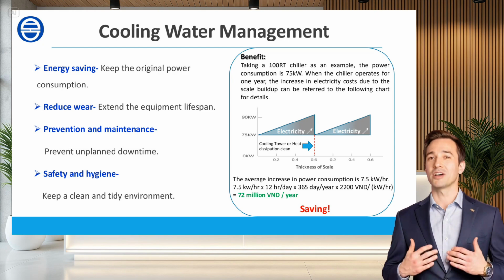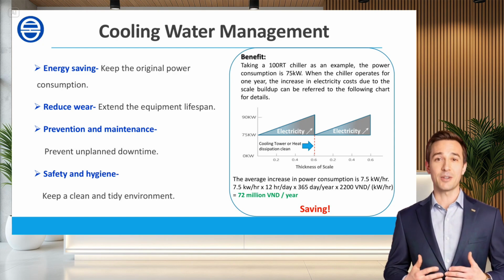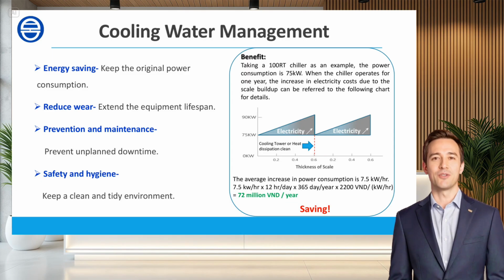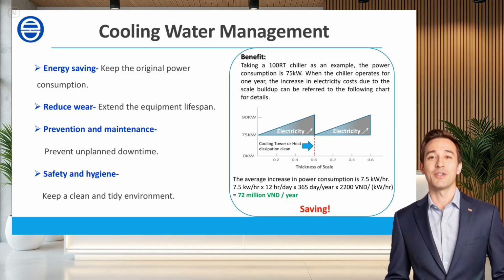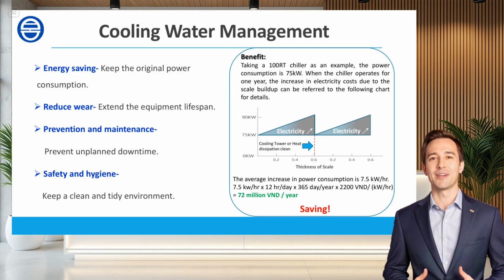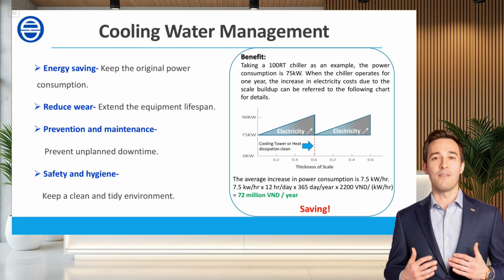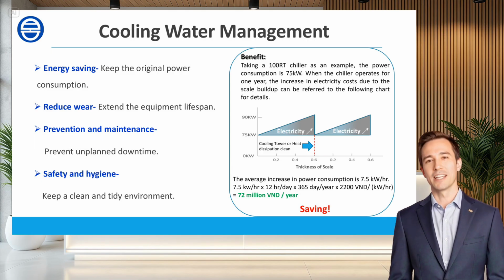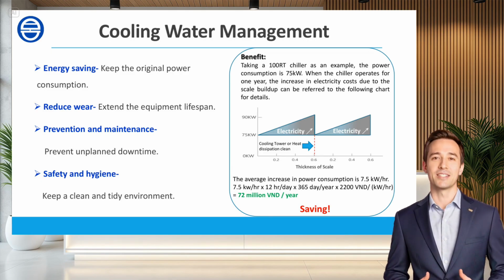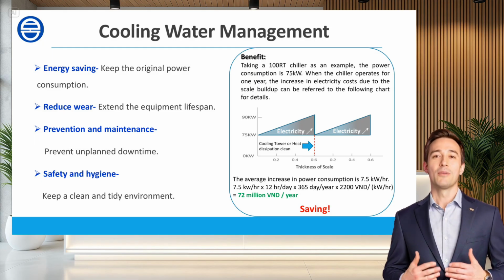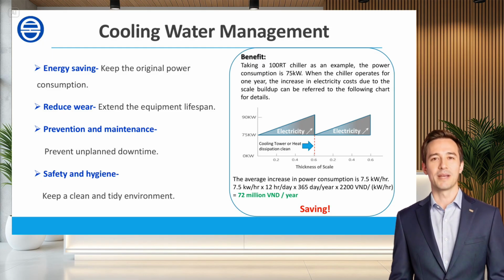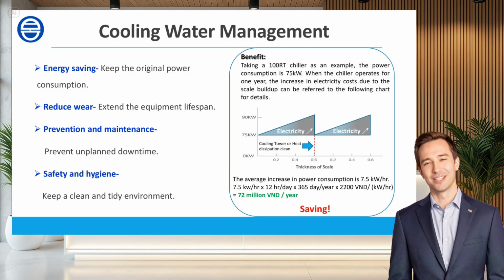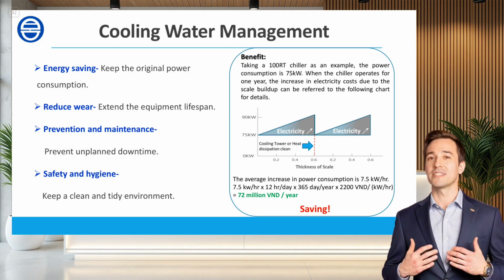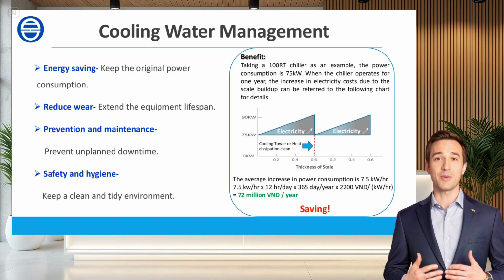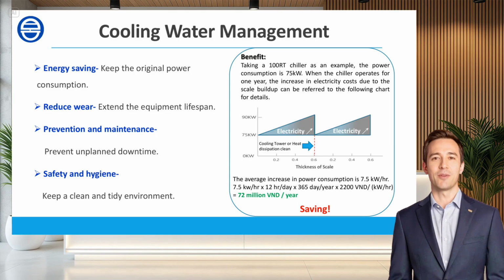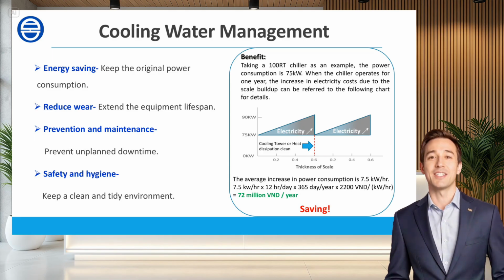Problem solved for now. But if the factory still isn't maintaining the cooling water properly, the same issue will keep coming back. And the more often you do acid cleaning, the more you risk damaging the equipment through corrosion. Eventually, you might end up with a leaking heat exchanger that needs to be replaced entirely, and that's not cheap. This kind of situation happens all the time in factories. But if scale buildup in the cooling water is properly controlled, production becomes more stable, your maintenance team gets fewer headaches, and most importantly, your boss saves a ton on electricity bills.